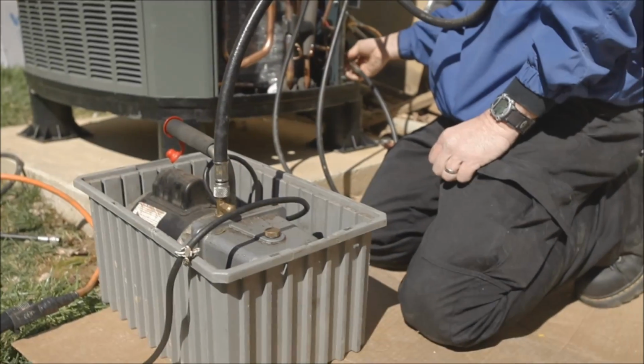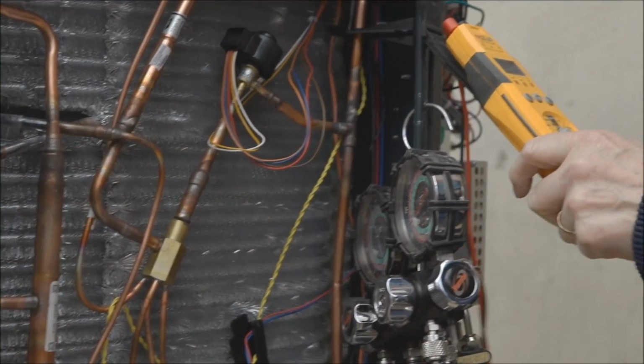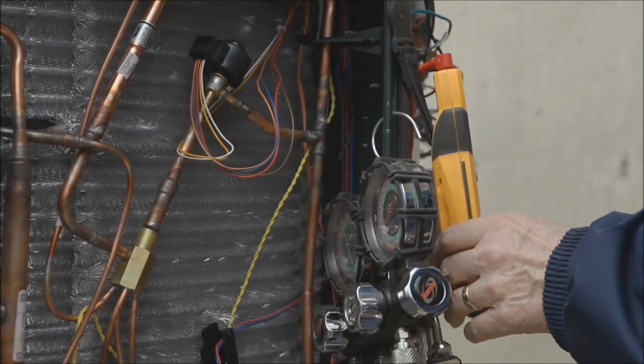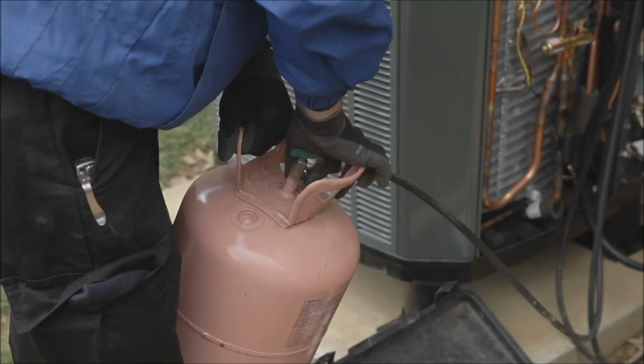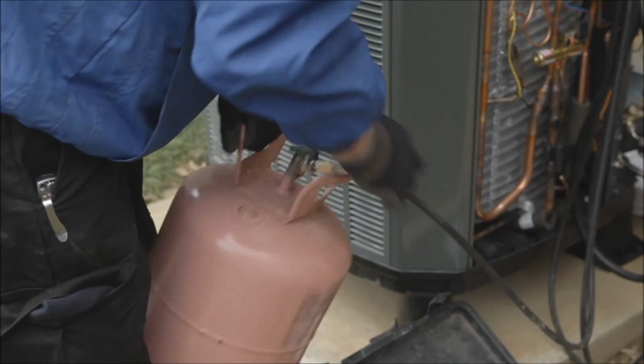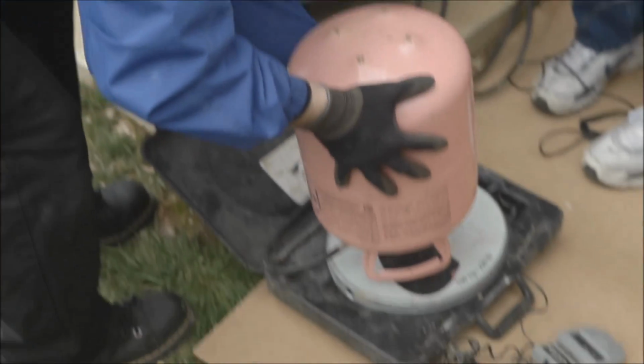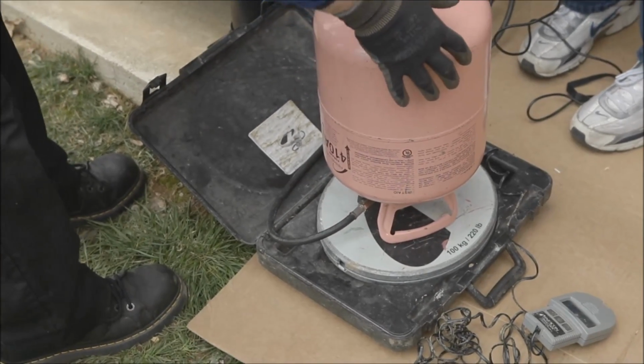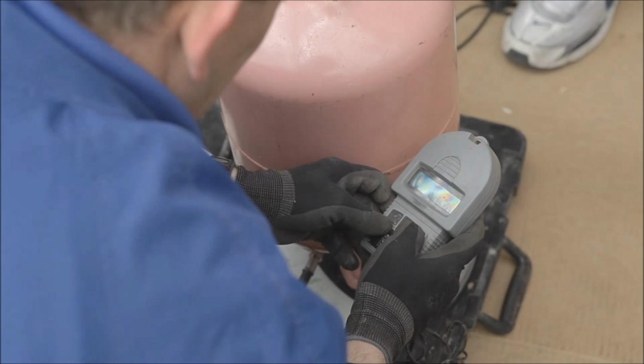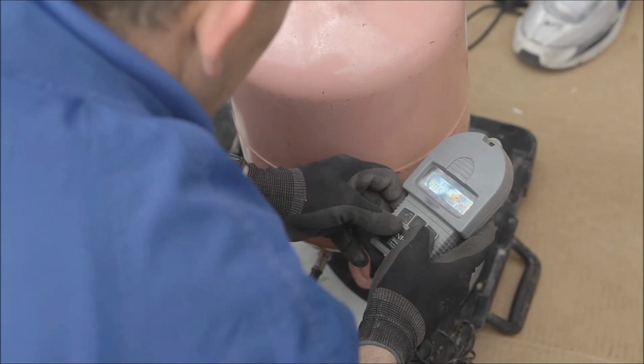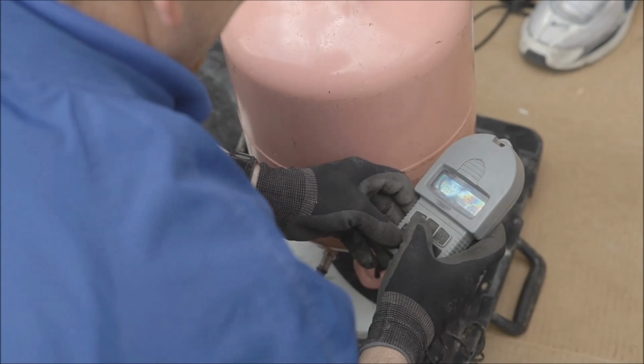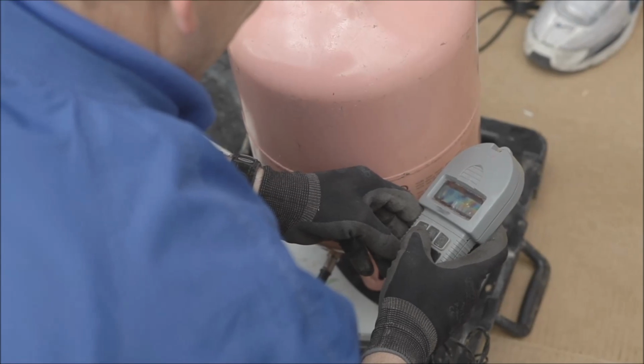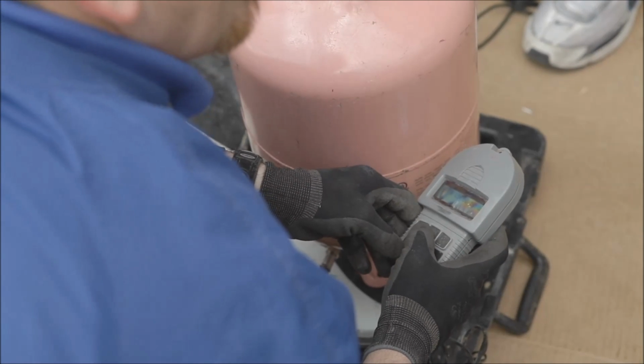To remove all air and non-condensables, the technician is evacuating the refrigerant lines using a vacuum pump. After evacuating the refrigerant lines, the unit valves are opened. Additional refrigerant, if required, is weighed in or added at this time. The system charge is then verified using the subcooling method. This is the only approved method for the XV20 variable speed.